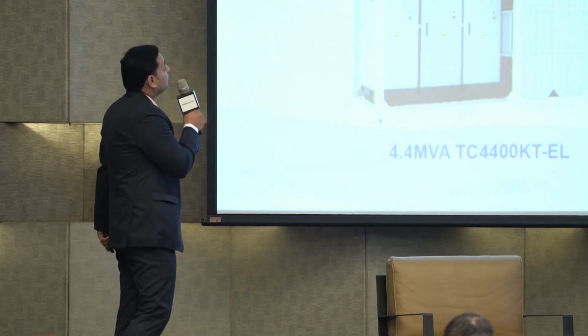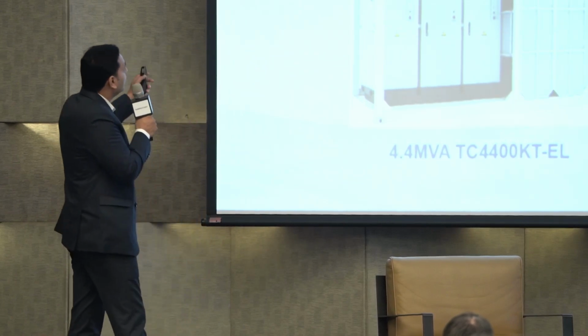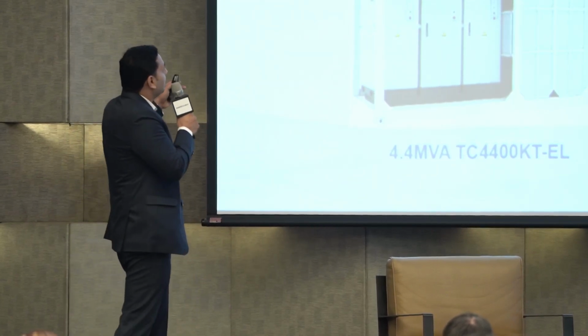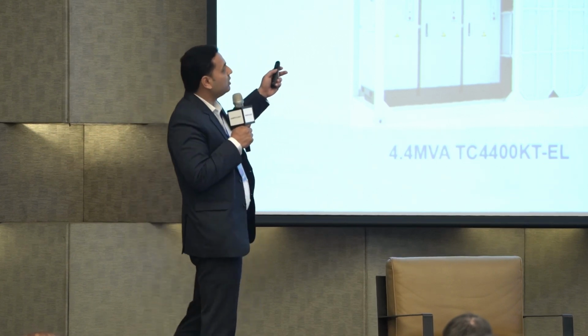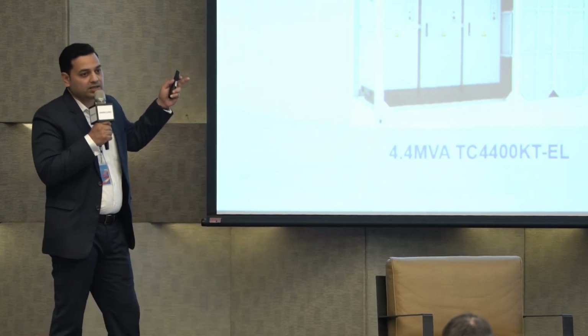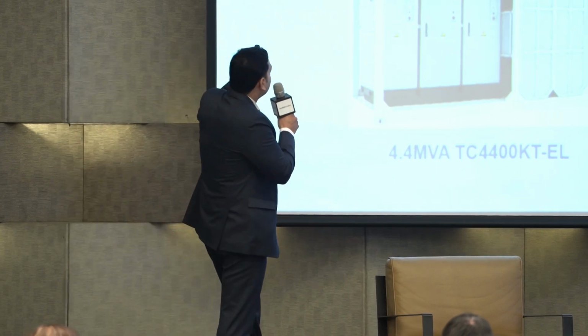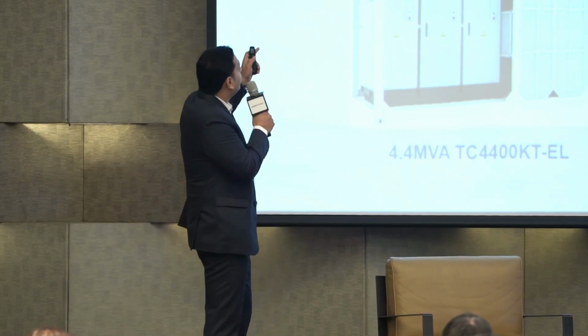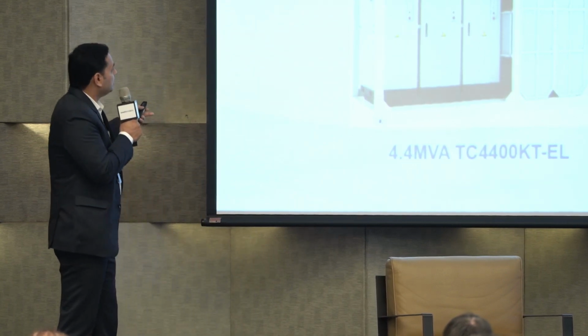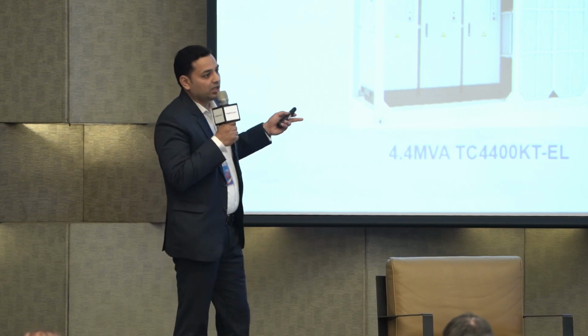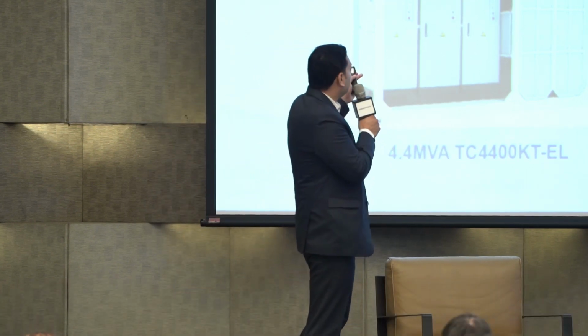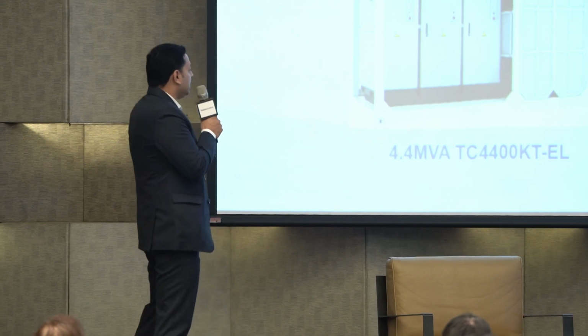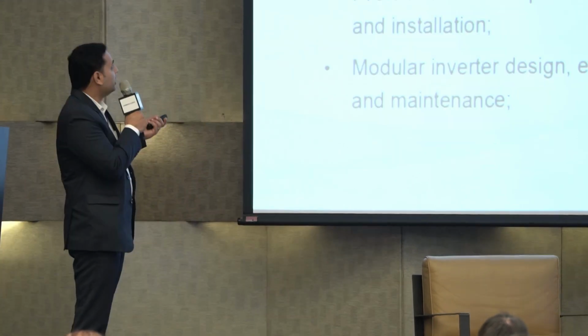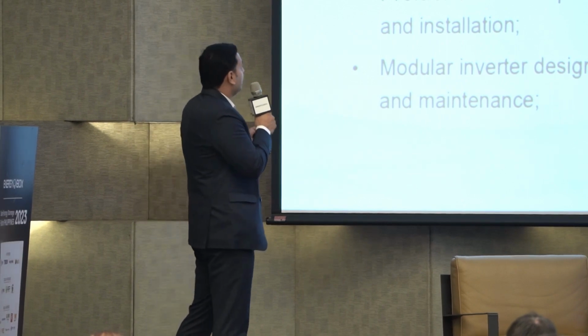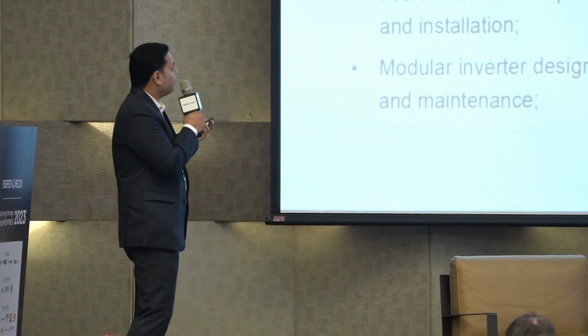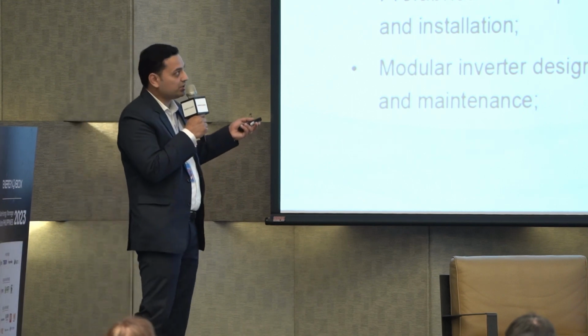Moving ahead to transformer turnkey station with central inverter. We have 3 solutions in this one. One is with 3.125 megawatt inverter, which is 6.25 MVA, a single transformer station, which consists of 2 numbers of 3.125, 1 transformer and RMU. The second one is 8.8, which comes with 2 numbers of 4.4 megawatt inverter, transformer and RMU. Similarly, efficiency levels are quite high, and high capacity will reduce the quantity of MV equipment, which will save the investment of the whole solar station.